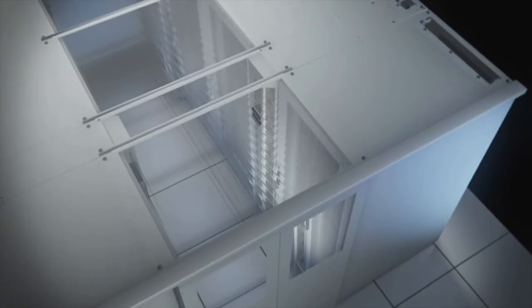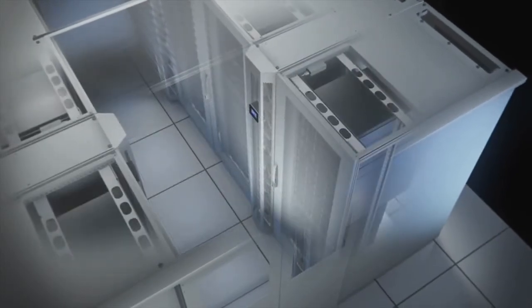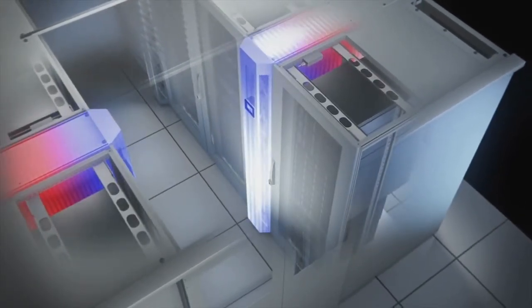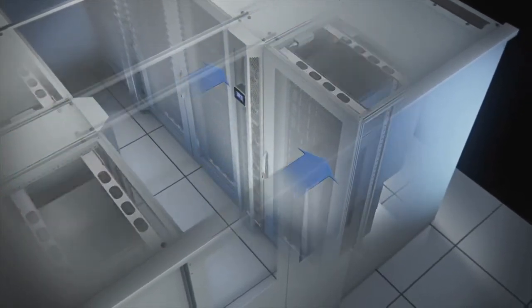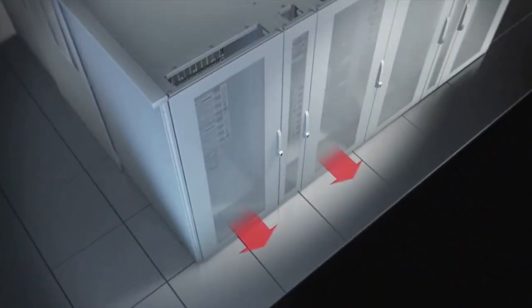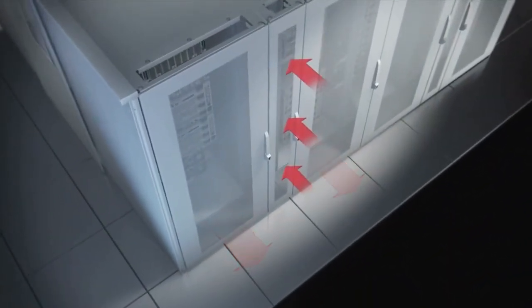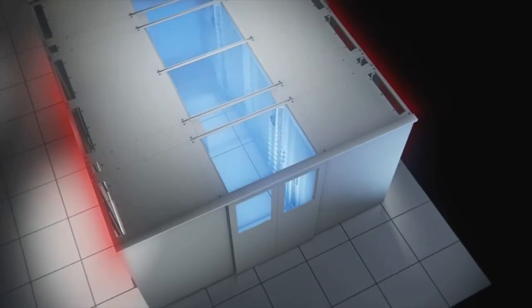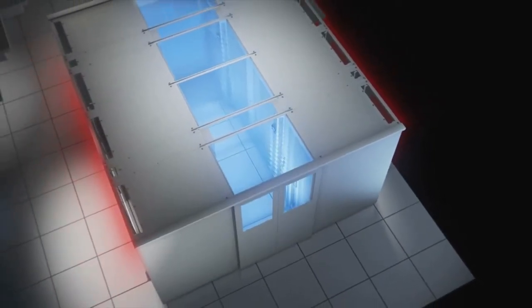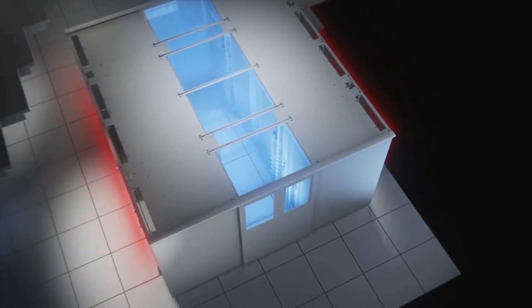Using the LCP inline configuration shown here, cooling can be aimed directly to the rack level. Cool air is forced into the aisle by 6 high-efficiency internal fans, and it enters the enclosures through perforated doors. After flowing over the components, the heated air flows out of the enclosure's perforated rear doors and back through the LCP's perforated rear doors. The fans recirculate the air through the air-to-water heat exchanger. Again, adding complete containment guarantees more consistent cooling.